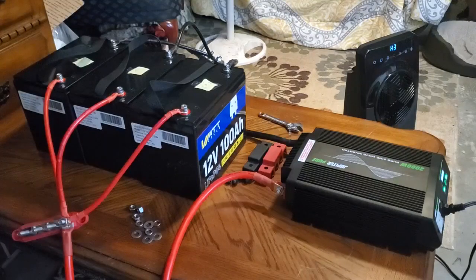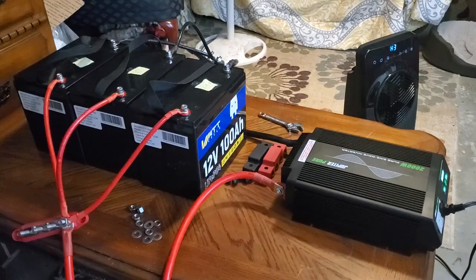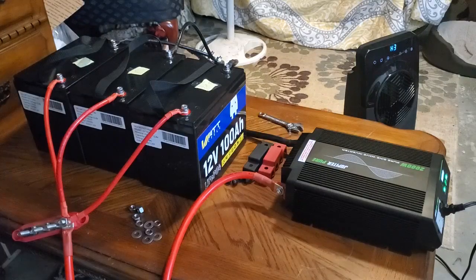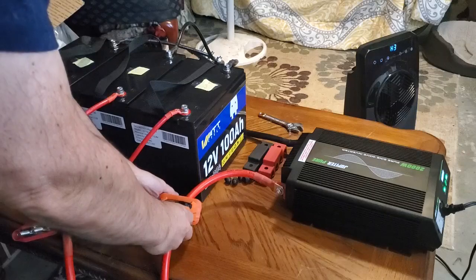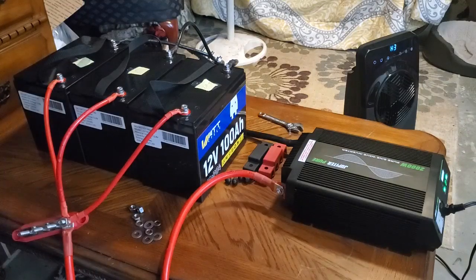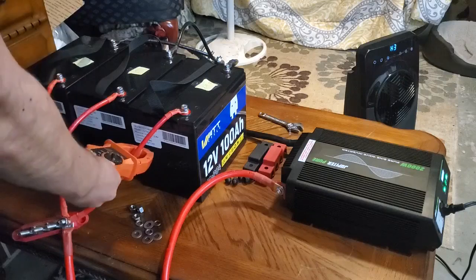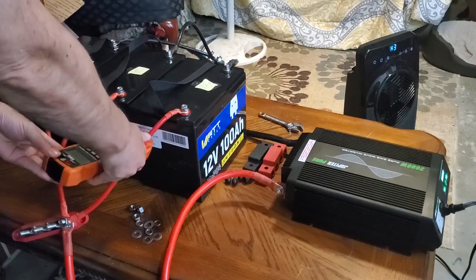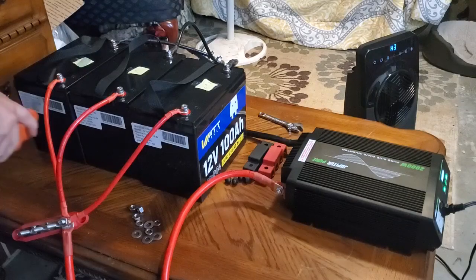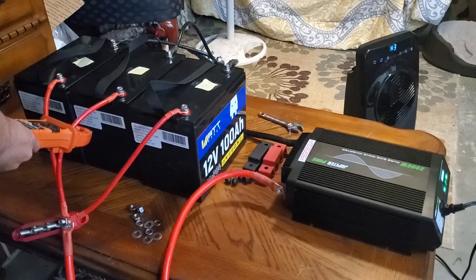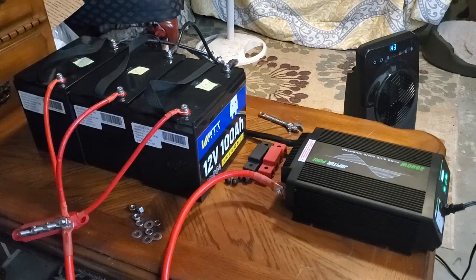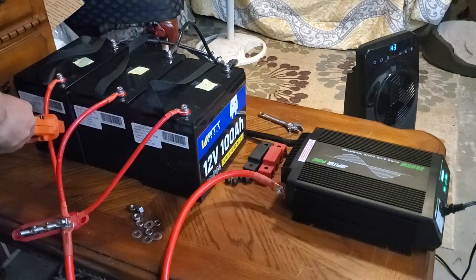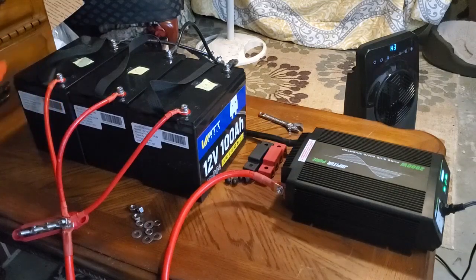10 minutes later, we are back. We're going to start taking some amp readings here. Starting with the bank amperage, of course. 115.7 amps on the bank. For battery number one, 38.1 amps. Battery number two, 37.6 amps. And battery number three, 38.1 amps.